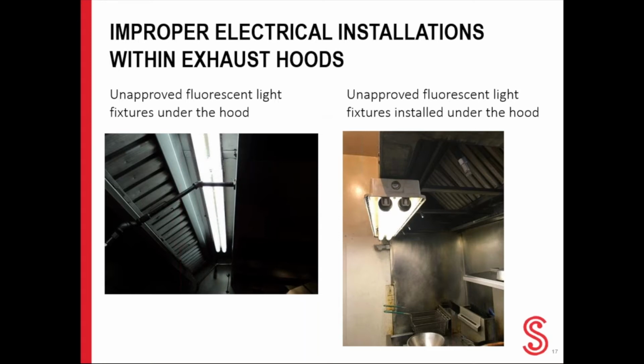These two fluorescent light fixtures installed in the exhaust hoods are not listed by UL for installation under a kitchen exhaust hood. The buildup of grease from grease vapors on the unlisted fixtures increases the fire hazard. To prevent the hazard of fire and property damage, the light fixture should be replaced by a contractor with new hood light fixtures specifically approved for such use, which would be UL listed. All electrical installations should conform to the current edition of NFPA, National Electric Code.